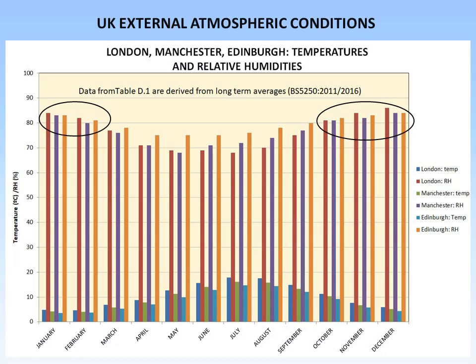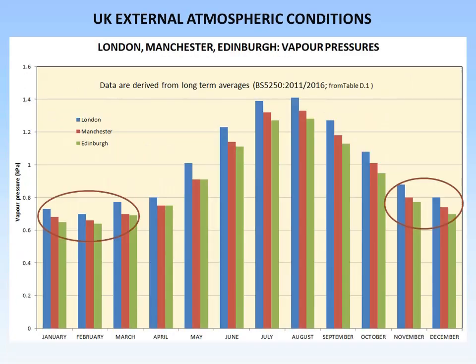First, we need to look at UK external atmospheric conditions. In the colder months, external relative humidities are very high — around 85%. In summer months they are lower, but still around 70% relative humidity. Converting those figures to vapour pressures, which directly measure the actual amount of vapour in the air, shows that during colder months vapour pressures are pretty low, whereas in July and August they are very high — effectively double those found during colder months.